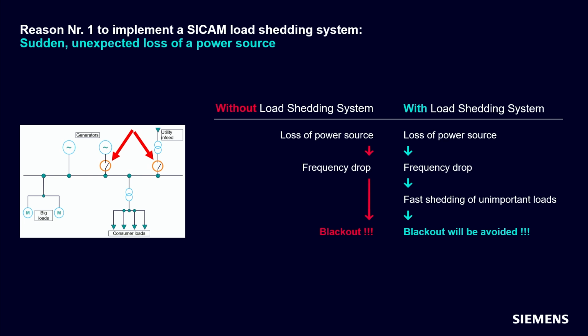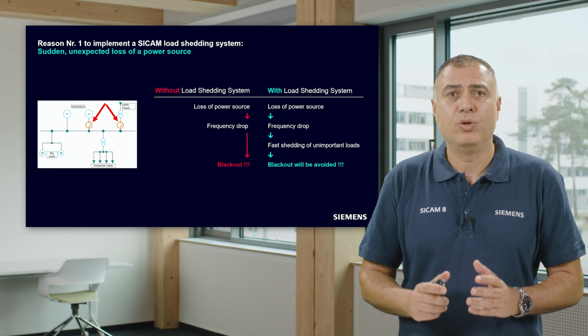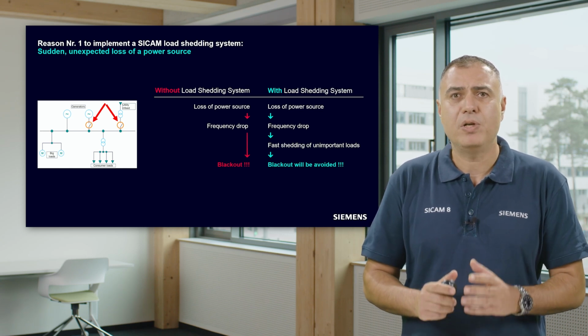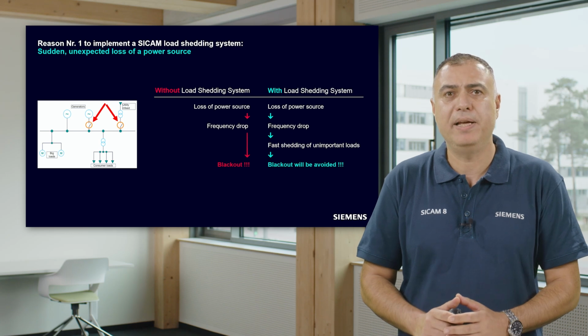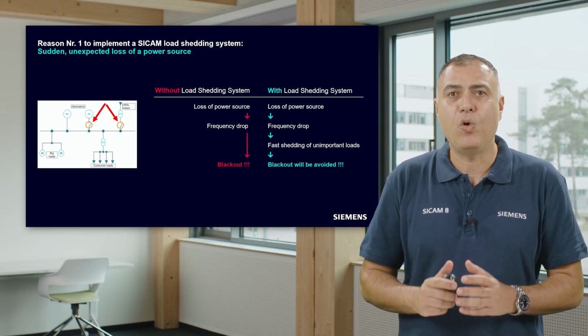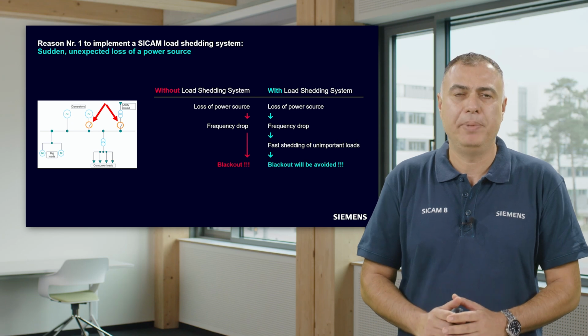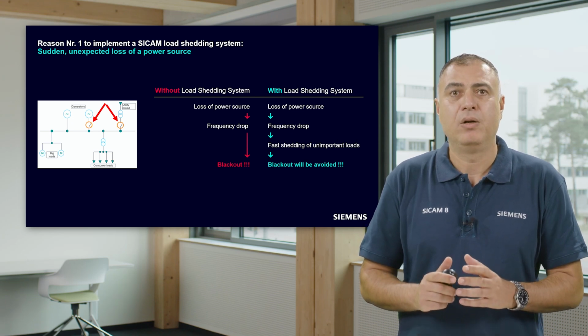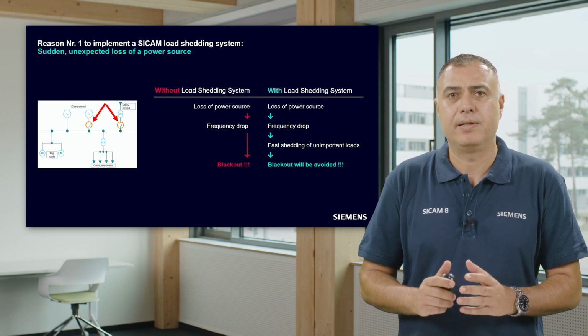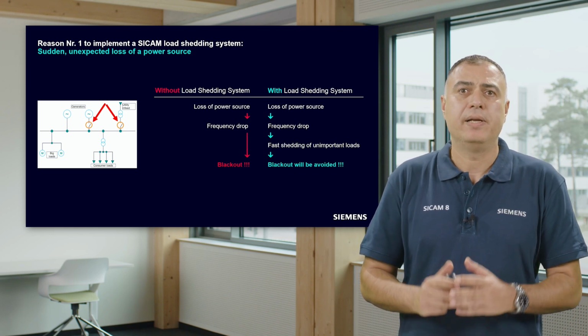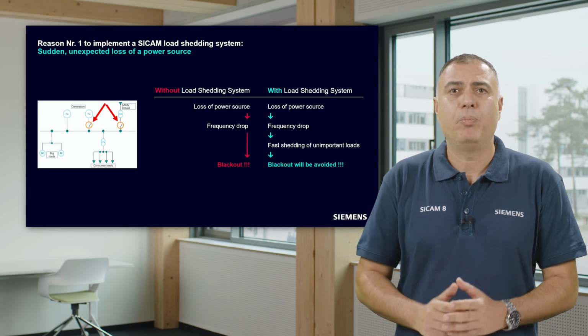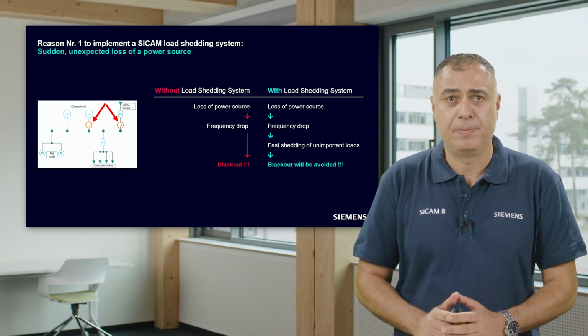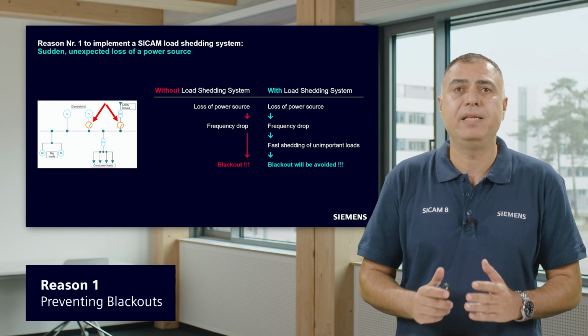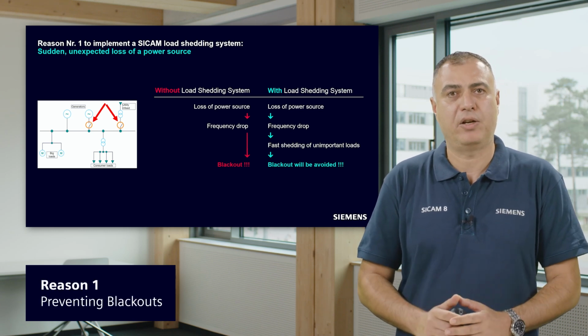So let's start with reason number one. It's a typical well-known use case. Imagine that this is your industrial power grid. If a power source like the infeeder from the public grid trips and there are no compensation measures, then the frequency will begin to decline. Depending on the characteristics of the industrial grid, this drop of the frequency will reach within short time the trigger point of all generator protection devices. This means a complete blackout for the entire production site.